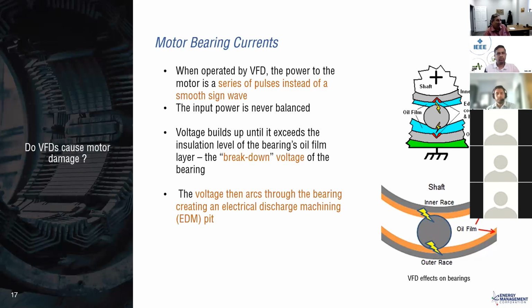Usually the harmonic content from a current standpoint is not too bad. It might be less than 5%, but that brings up another question. When you apply an inverter on a motor, most manufacturers will say that you don't have to derate the motor necessarily, but you do need to give up some of the service factor. Right. There is a little bit of heating there. Yeah. So thank you for the question.